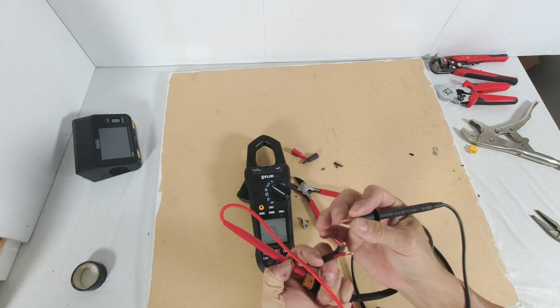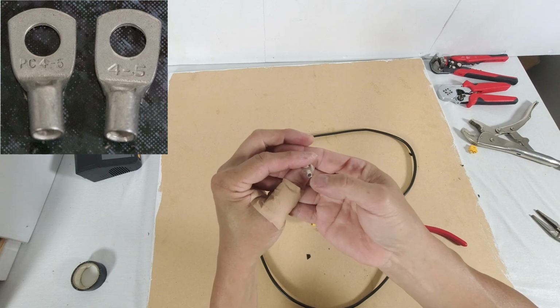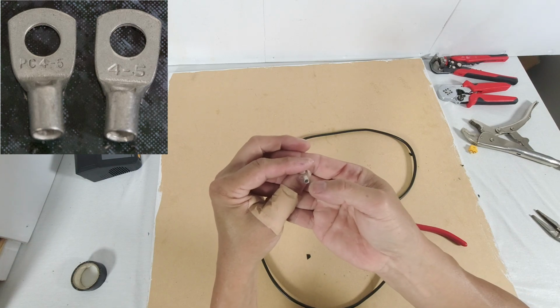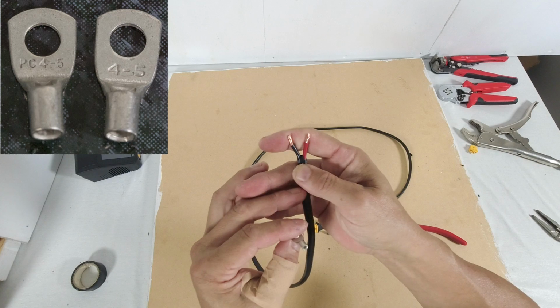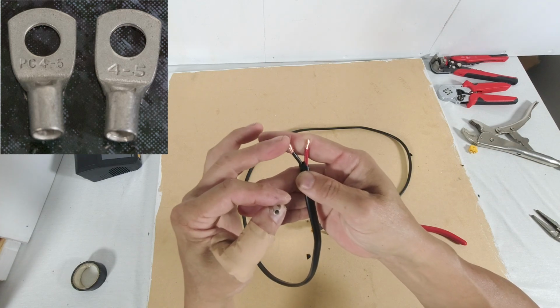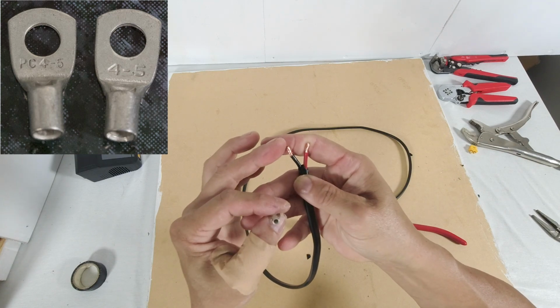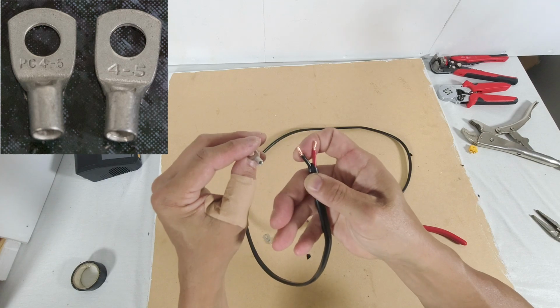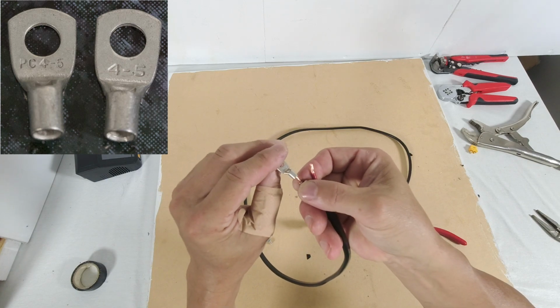Check there's no short circuit. There's no short circuit. This lug takes a 4mm square cross-sectional wire, whereas this automotive cable has a cross-sectional area of 2.9mm square, so it's a bit smaller than what's recommended to fit in here.